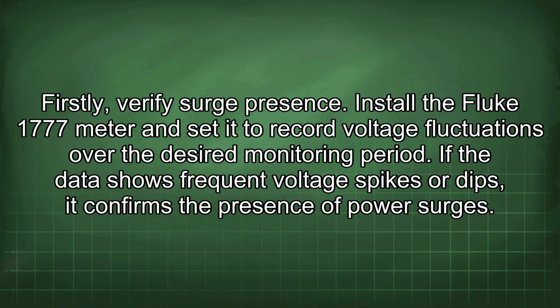Firstly, verify surge presence. Install the Fluke 1777 meter and set it to record voltage fluctuations over the desired monitoring period. If the data shows frequent voltage spikes or dips, it confirms the presence of power surges.